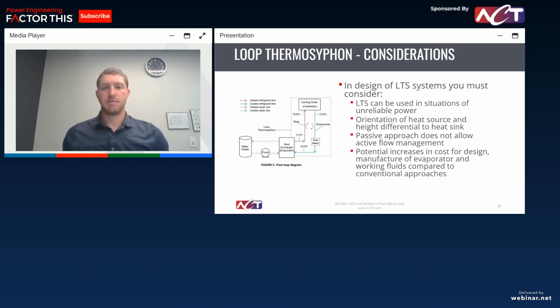So some things when we're looking at loop thermosyphon, one thing is you can use this in places of unreliable power. We had one application where they were essentially running on generator power a large percentage of their time. So loop thermosyphon was an ideal solution for that application because it uses such little power. You don't have a pump. We did run a fan in that situation, but it's much smaller power, so much better efficiency. You're not throwing money away on that generator as much.